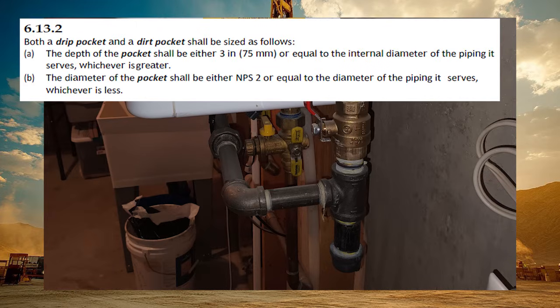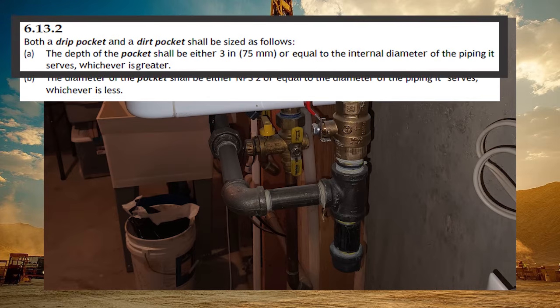The next clause deals with sizing. We're going to break it down into two parts. 6.13.2: Both a drip pocket and a dirt pocket shall be sized as follows. A. The depth of the pocket shall be either 3 inches or equal to the internal diameter of the piping it serves, whichever is greater.